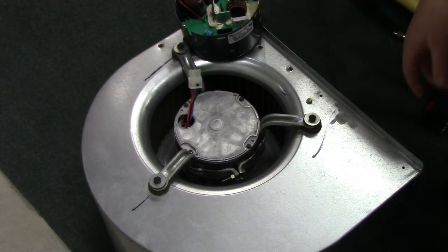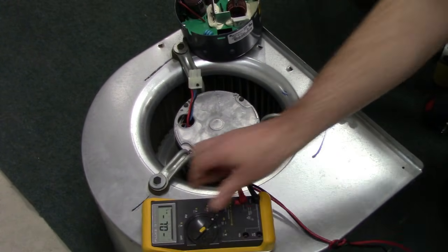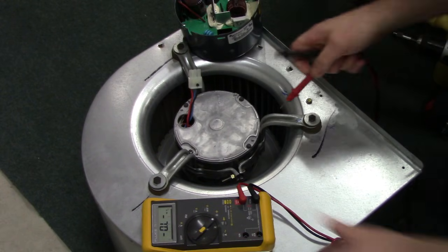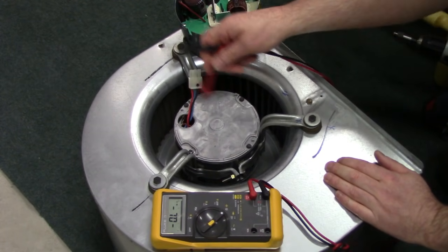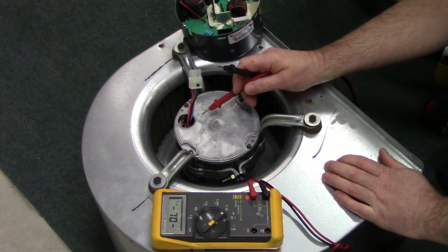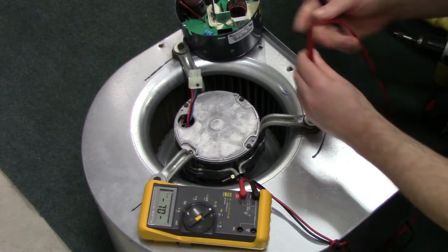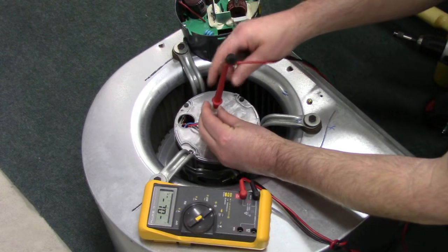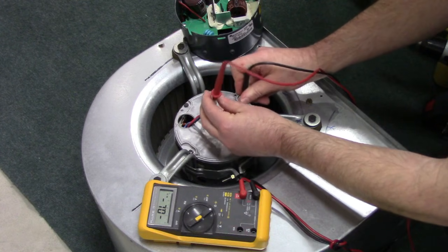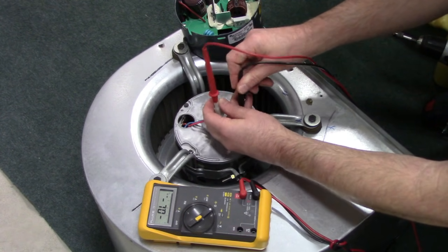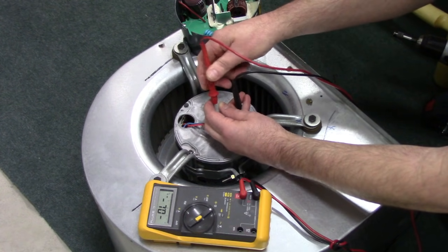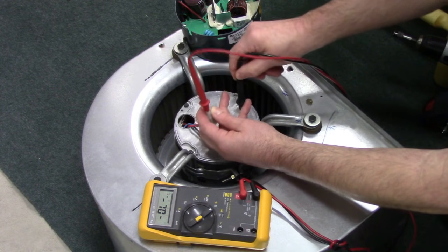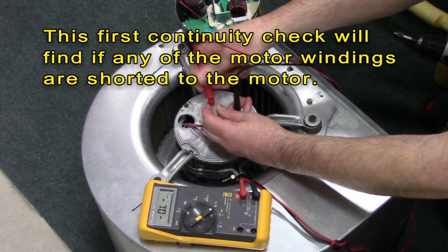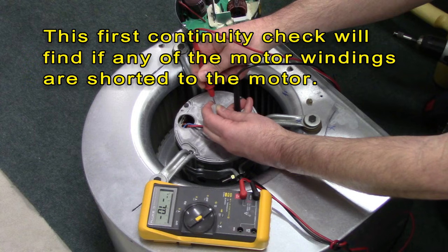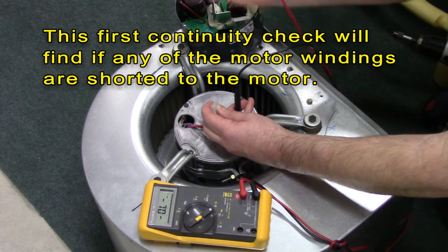So that's the first check, the first physical check. Next check on the motor is to check if there's any shorts or if there's any opens in the phase windings. And to do that, first thing you do is make sure there's no continuity between any of the 3 phase wires and the case of the motor. So you don't want to see any continuity, you want to see infinite resistance on all of these. And that's what we've got.